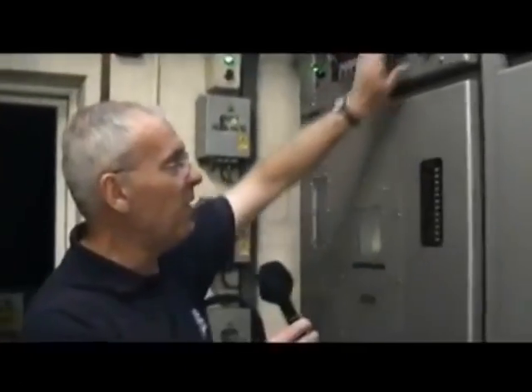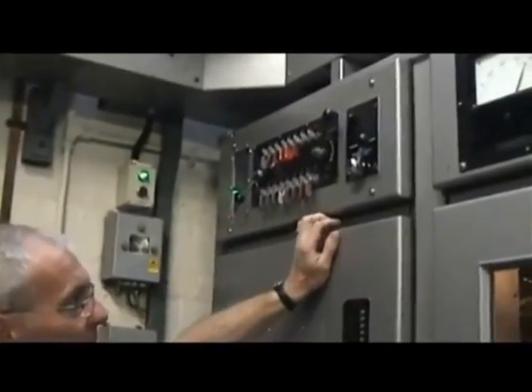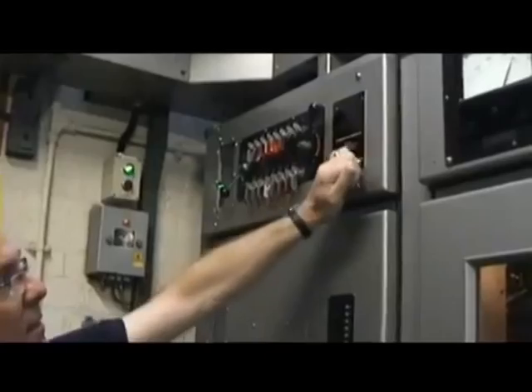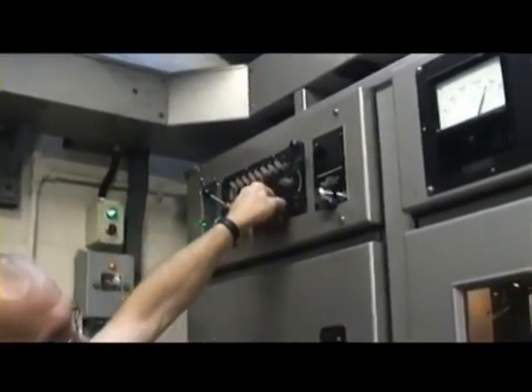Let's wander around the side. I'll open it up so you can see the tubes on. We need to take the power supply off, or the HV power supply. We need to open the isolator. Wait for the motor to run through, and let's get some earths on. That gives me access to the key, or one of them. And if we open this door here, I have a good view of the valve filaments.